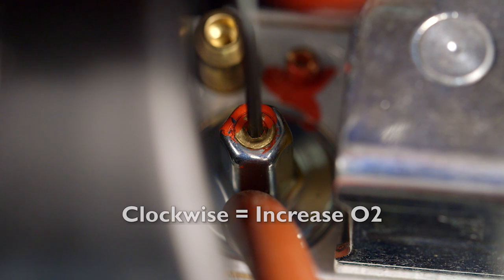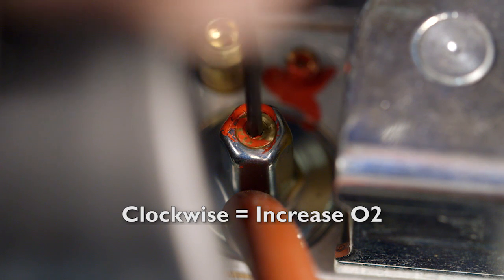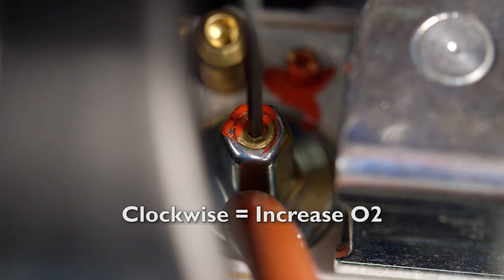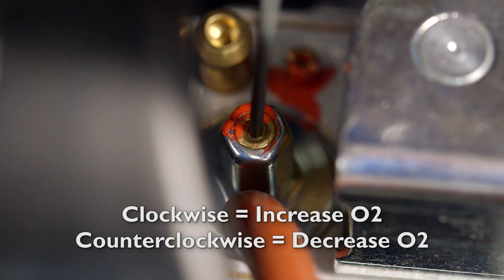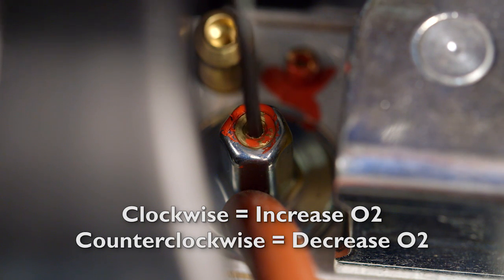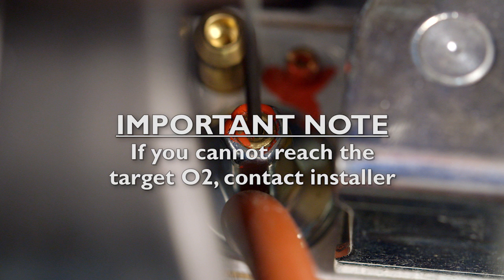If you need to, you can correct the value on the boiler by turning the adjustment screw clockwise to increase the O2 value, or counterclockwise to decrease O2. Repeat this step-by-step process for all gas valves in the boiler. An important note: if you cannot reach the target O2, contact your installer.